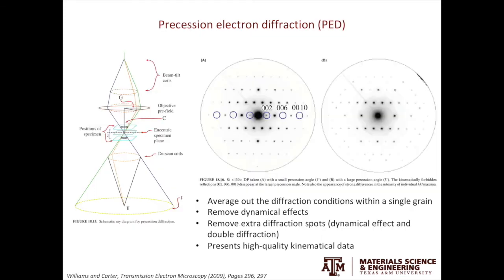Precession electron diffraction, or PED, is a technique available in our lab. During PED, the beam precesses or rocks to form a cone. The main advantage is that it removes dynamical effects and extra spots that are supposed to be forbidden, giving high-quality kinematical data. In the example shown, with a small precession angle you still see some forbidden reflections from the dynamical effect, but with a larger angle those spots disappear.